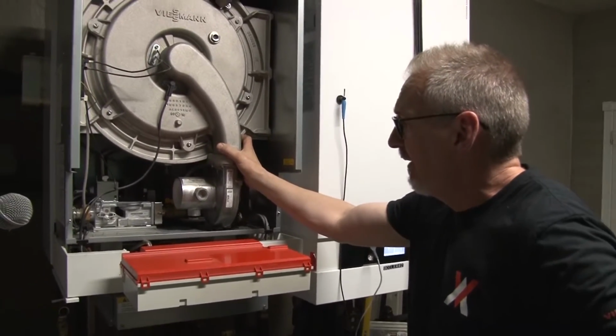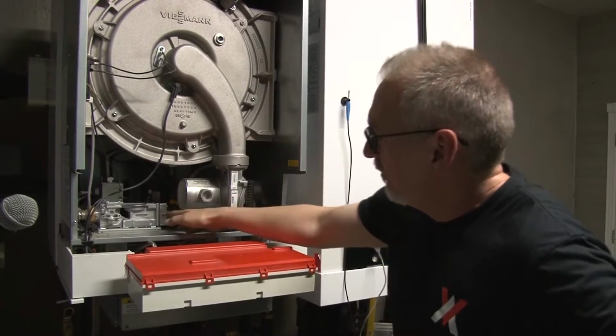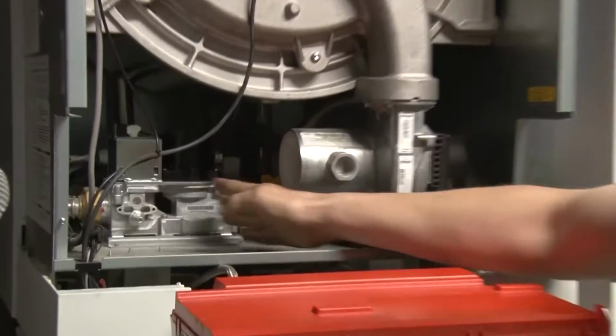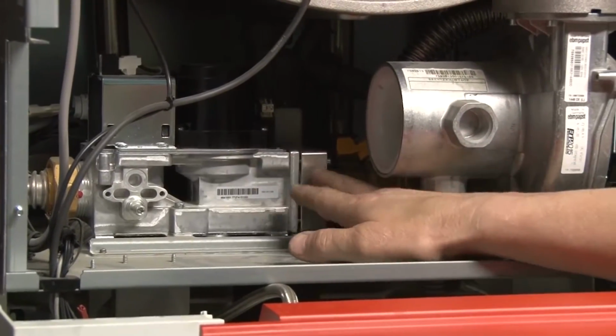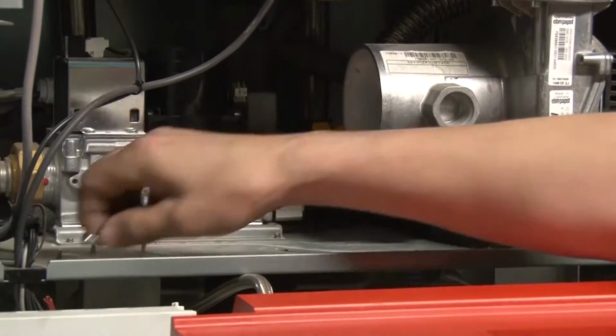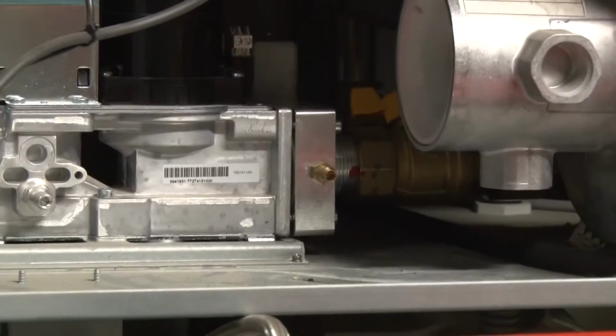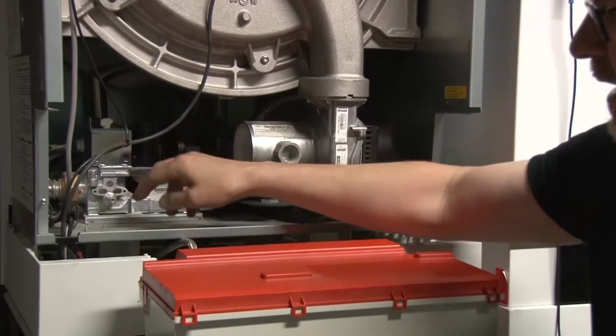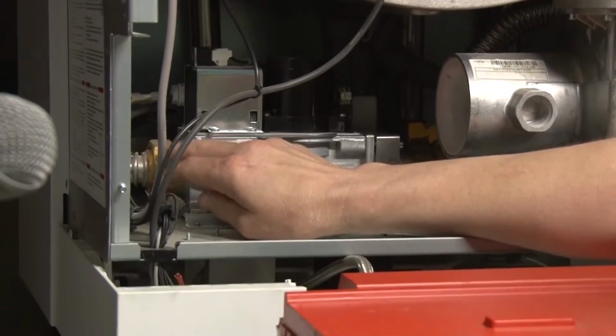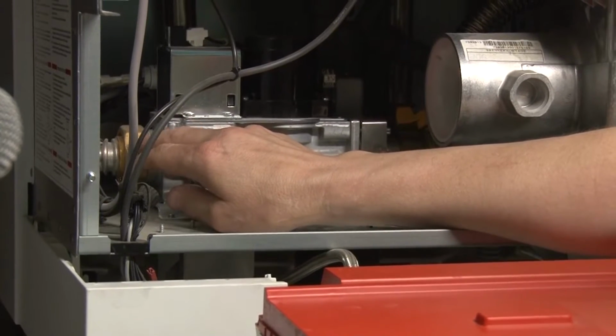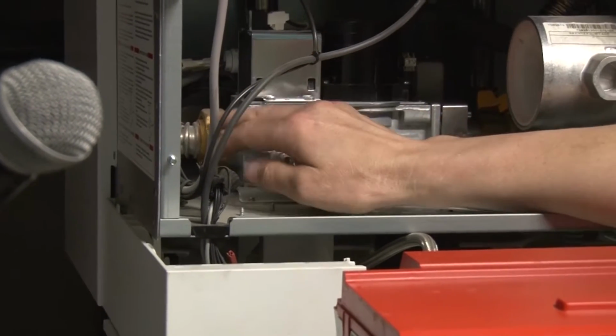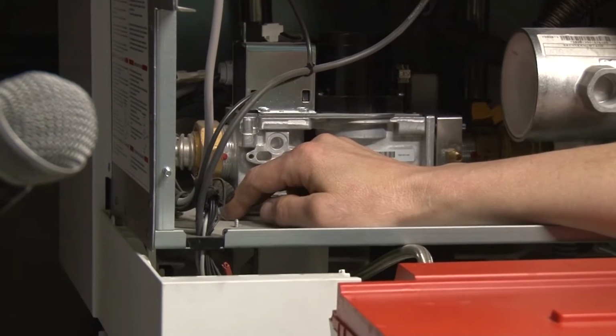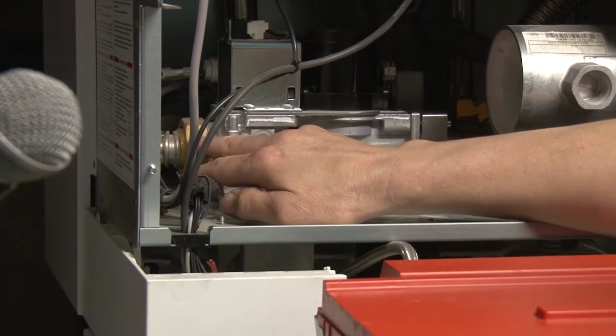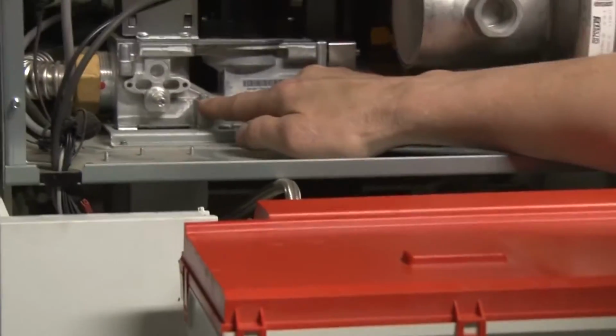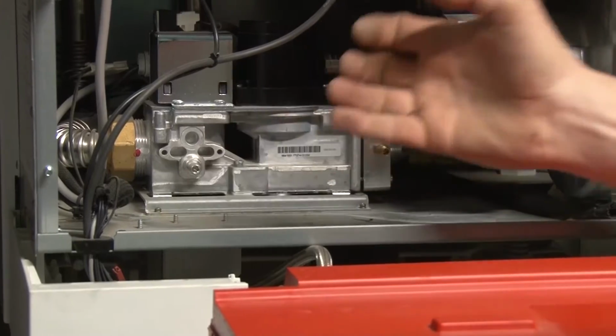My recommended method from the manual would be to basically, this little block on the downstream of your gas valve here, there are a couple of 4mm bolts. I've taken a couple of them out, and in the manual they'll recommend to pull the burner out this way. I've also taken the nut off here on the gas valve. Important when you're doing this, make sure the gas is isolated, so that when you open this up, if that's open, you're going to get a lot of gas moving through this little 1-inch corrugated stainless steel pipe. But you can crack the nut here, and basically there's another 4mm bolt right in here that you would have to back off to remove that whole gas valve.